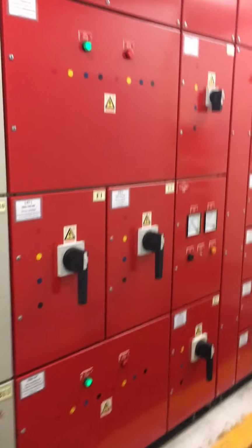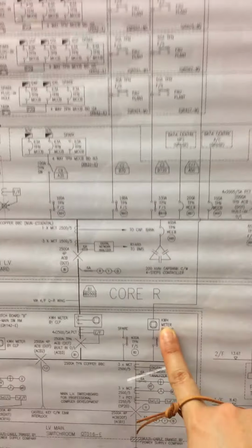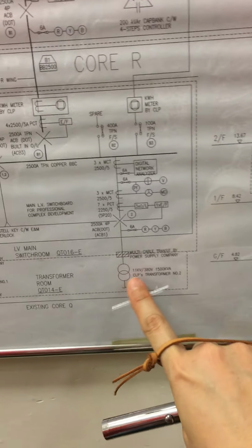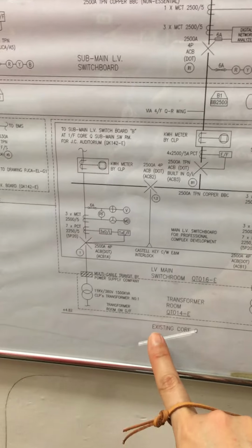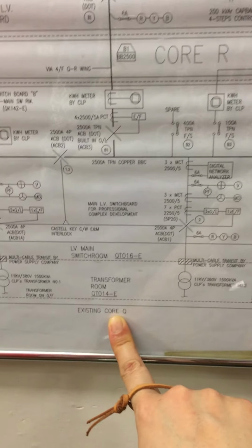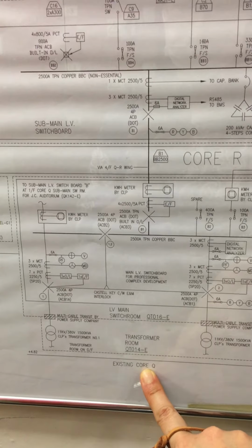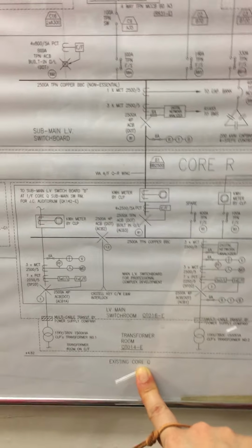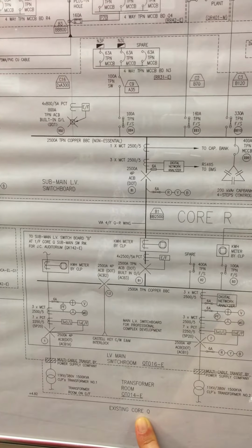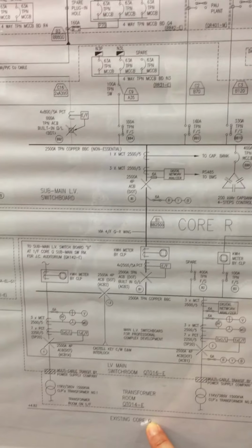For this switchboard, we cannot find the energy meter here because for PolyU there is no tenant, only landlord. So there will be only a meter here. Okay, so the transformer room is on the ground floor in core Q, and if you remember, this is the 3rd floor. So according to the CLP, it is required that the main LV switch room should be directly adjacent to the transformer room, right? So it seems to be not right to have the main LV switch room on the 3rd floor.